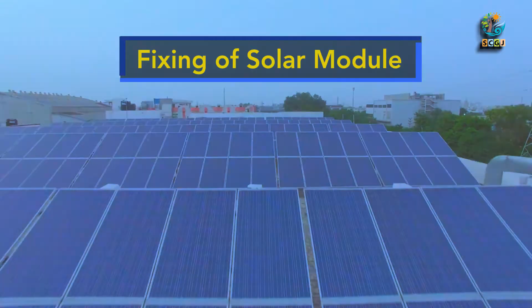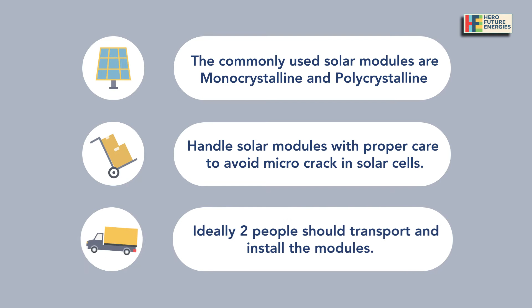The commonly used solar modules are monocrystalline and polycrystalline. Handle solar modules with proper care to avoid micro cracks in solar cells. Ideally, 2 people should transport and install the modules. While tightening purlin nuts, washers and bolts, make continuous smooth action using a calibrated torque wrench, which should be set at correct assembly torque.